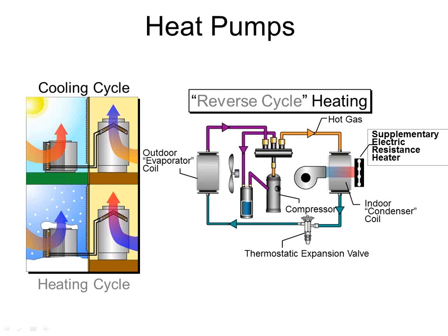I'm going to see if you guys can see my little spotlight red dot on the screen. Up on the top here, we have a summertime condition. On the left side, where my red dot is, I have a condensing unit. On the right-hand side, I have a fan coil or a furnace or whatever with an evaporator coil in it. That unit's job is to suck air from my house or my building, remove heat from that air into my refrigeration, and send it to the refrigeration pipes outside where I can reject the heat to the outdoors.